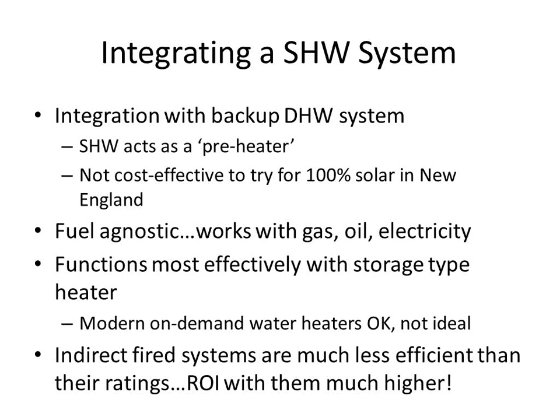We found it's really not cost effective to try for 100% if your expectation is year-round hot water in the quantities we're accustomed to. The problem isn't collection capacity—collectors are relatively inexpensive. It comes down to storage. In wintertime, you'll have a couple weeks a year with very little solar energy on the home: cloudy weeks, weeks with a couple feet of snow. So you'd need a system storing several weeks worth of thermal energy to ensure hot water for showers and laundry through the winter. Storing that much hot water and insulating it well enough to avoid standby losses over a couple weeks simply isn't cost effective, so we don't try for that.